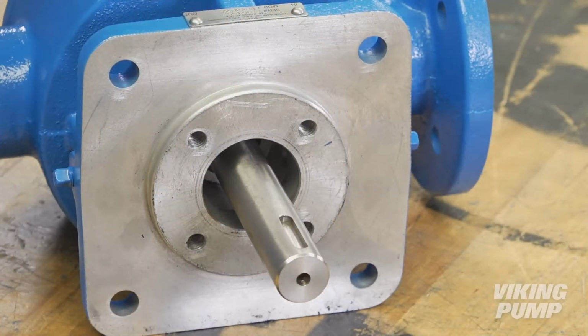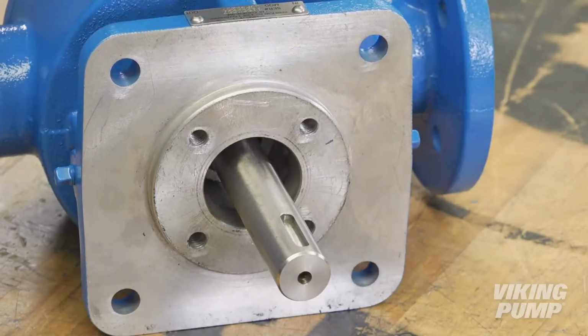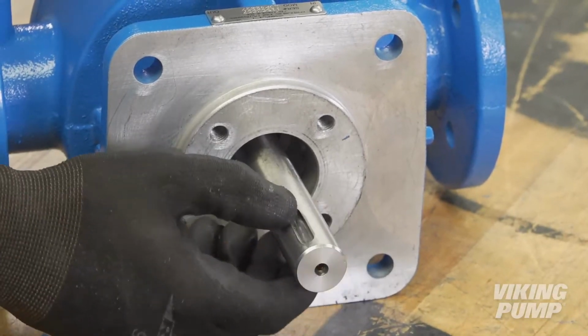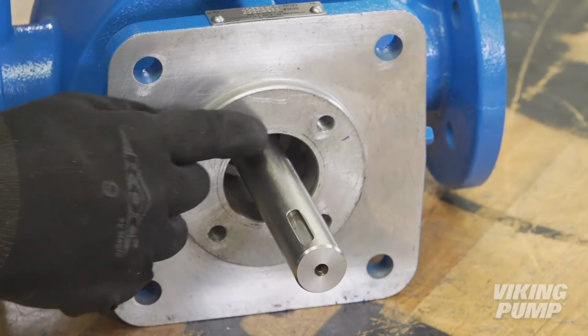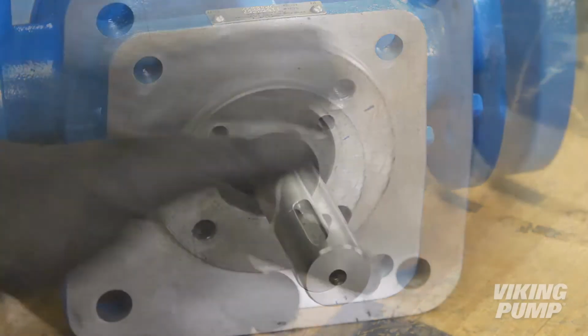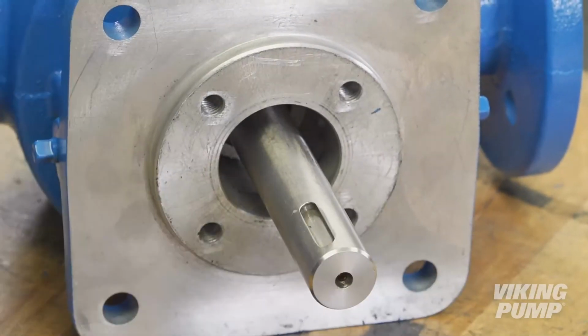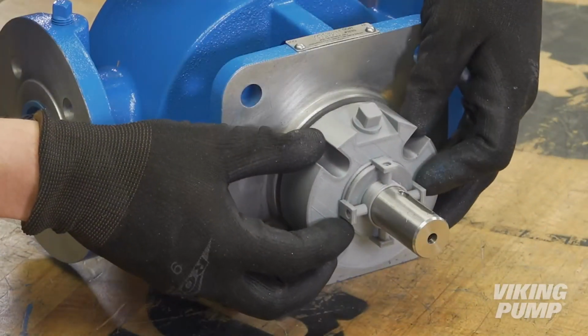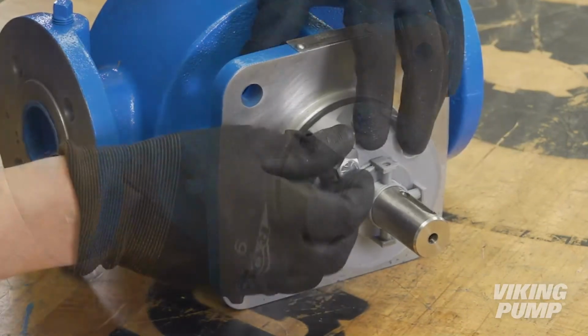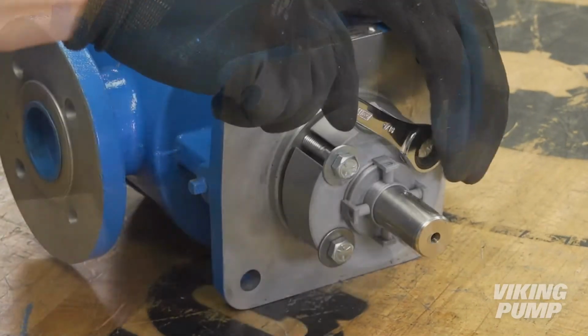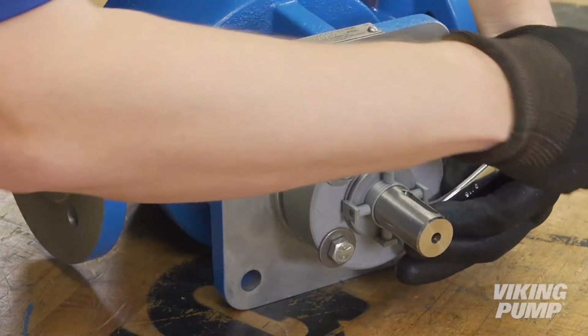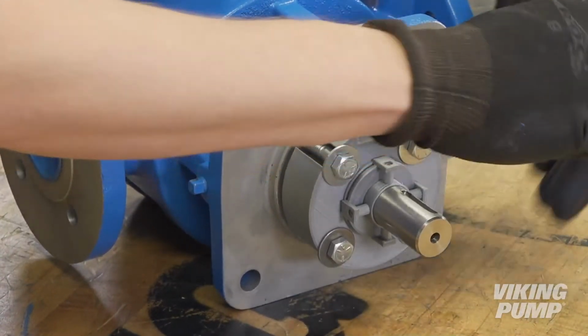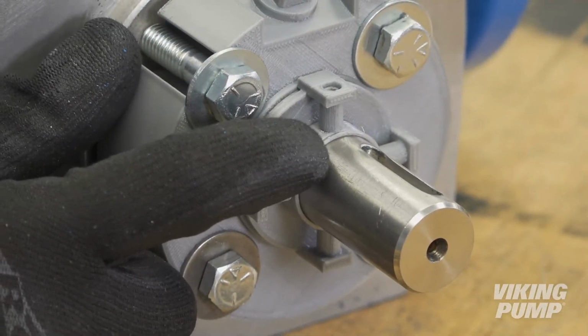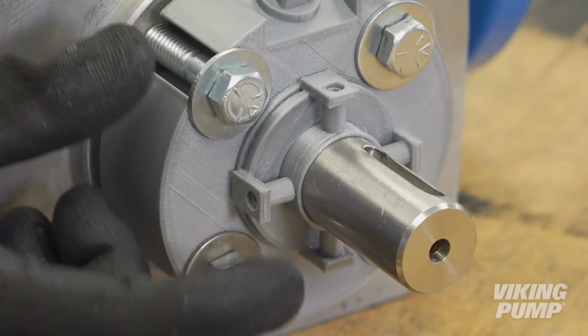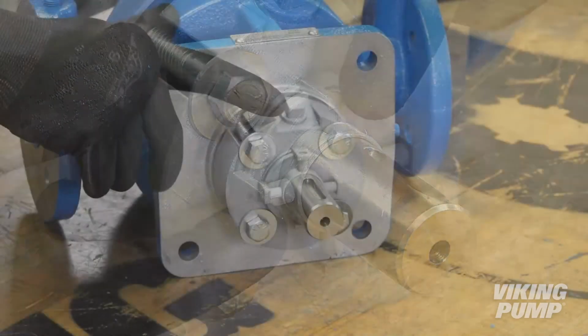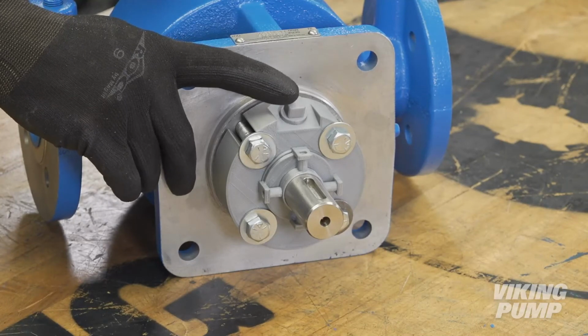For cartridge seal installation, first make sure the shaft and face of the seal chamber are clean and free of burrs or scratches, which may damage the seal or prevent sealing. Coat the shaft and O-rings with compatible lubricant. Slide the seal along the shaft and against the seal chamber face. Install the seal mounting cap screws and tighten evenly. Evenly tighten the seal collar set screws to set the cartridge seal to the shaft. Remove the seal spacers. Attach any auxiliary seal flush lines as needed.